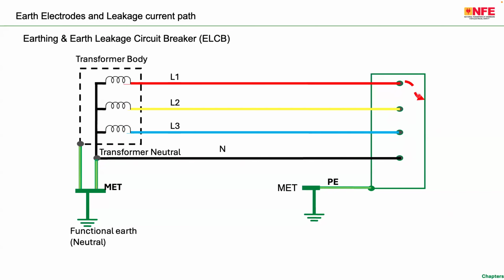In case of a fault in the equipment where I'm moving the cursor, or there is a leakage in this particular equipment, the current will flow through the PE conductor, through the earth electrode, through the general mass of earth, through the neutral earthing of the transformer, and back to the source. So basically, there is a current flow through the PE conductor, and that current is measured in an ELCB, earth leakage circuit breaker. The name earth leakage means there is a leakage going to the earth through the PE conductor.